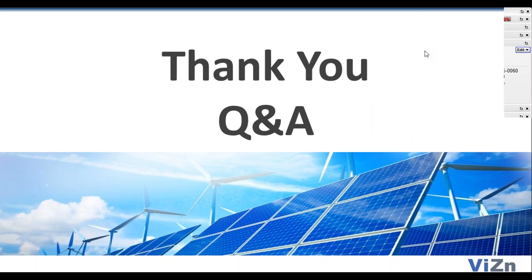The next question is about operations and maintenance — what is the annual O&M? For us, we have an annual service to come and revisit, looking at the balance of electrolyte and doing a general QA/QC on the system. So once per year we visit our systems. We also have 24/7 remote monitoring that helps us educate our service team and deal with any issues that may come up.